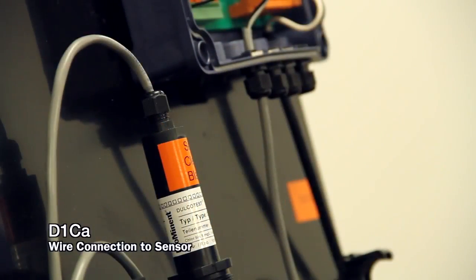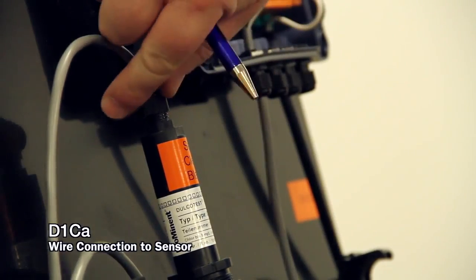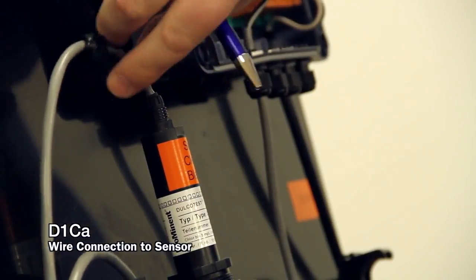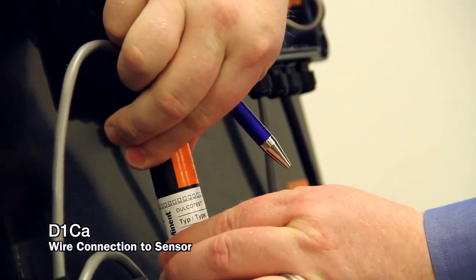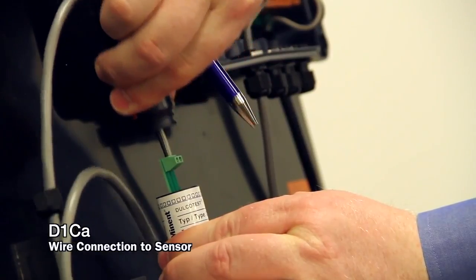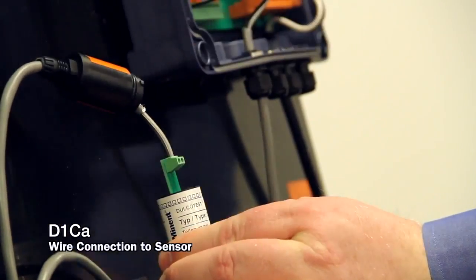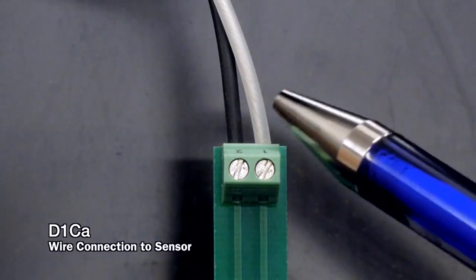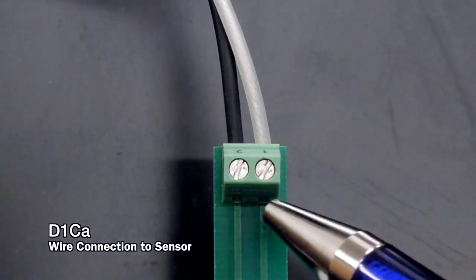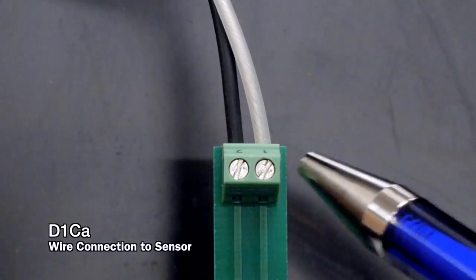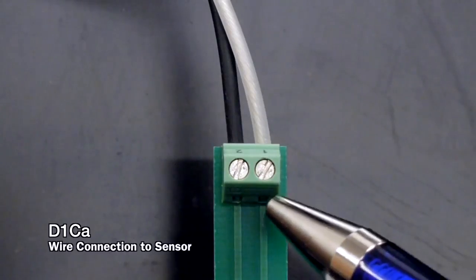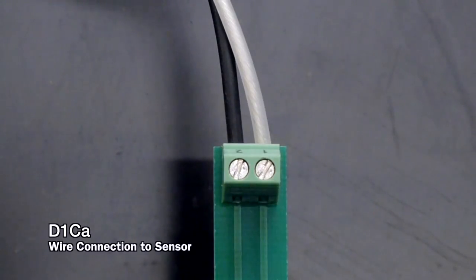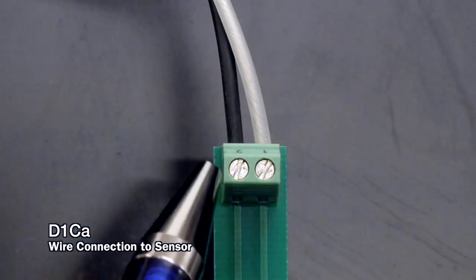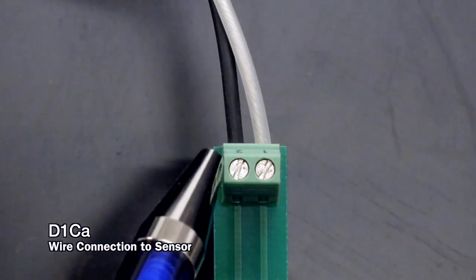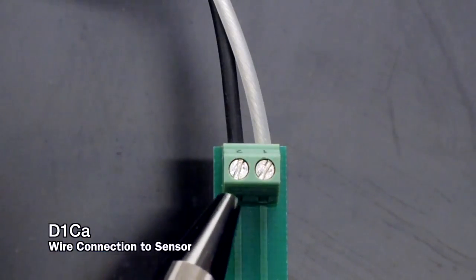Okay, so just to see how those wires are connected to the amperometric sensor, we'll loosen our strain relief here. To open the sensor and expose the terminals, it's a quarter turn. Pull that up. So we have the white or clear wire connected to terminal 1, which is coming from terminal strip X2 number 9, and the black wire, which is connected to terminal 2, which is coming from terminal strip X2 number 10.